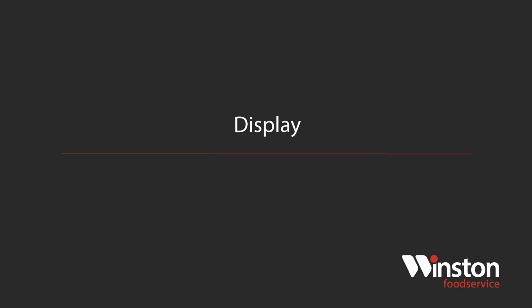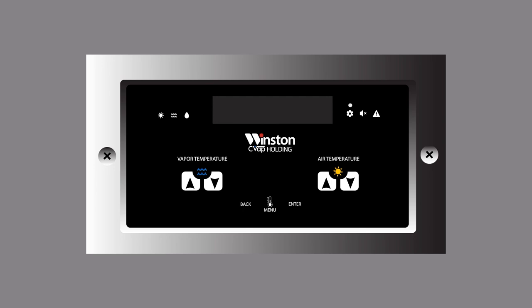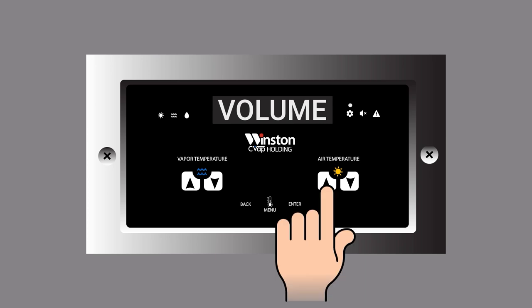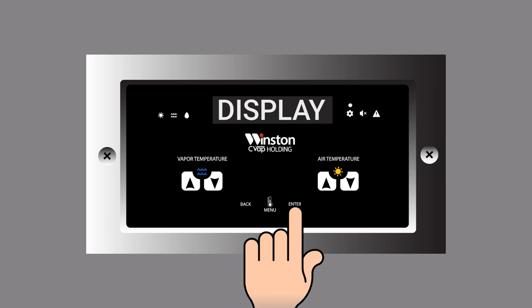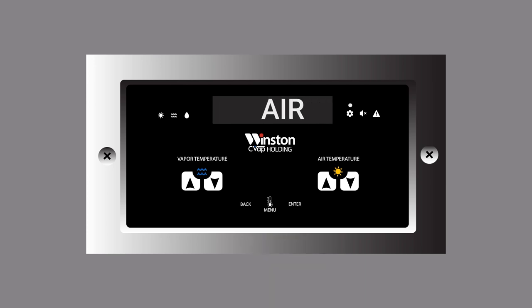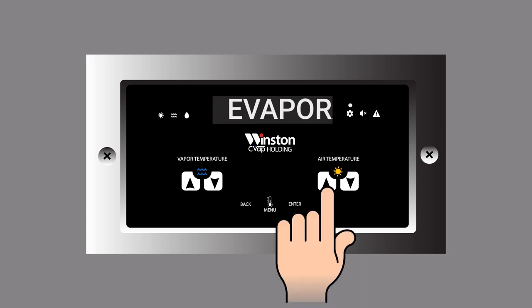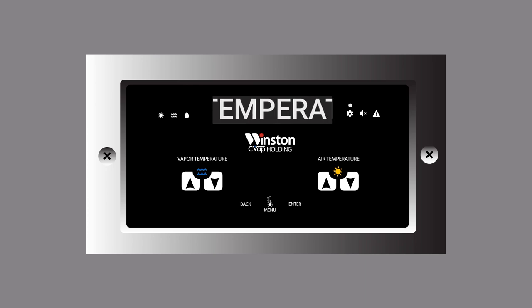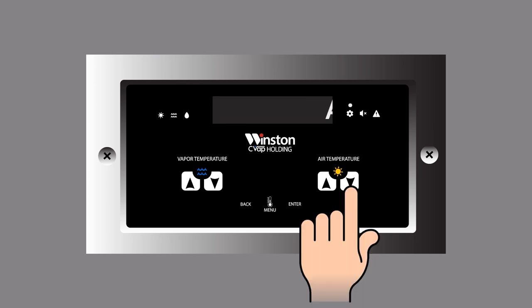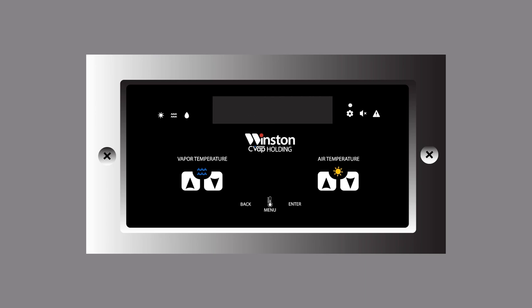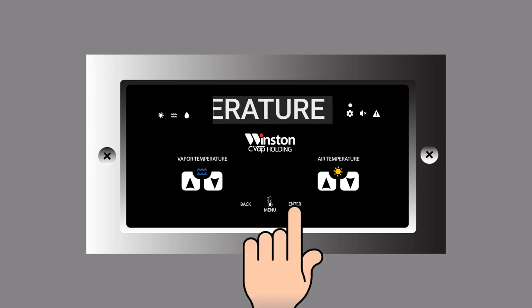Display. This allows the user to set the displayed temperature to either the vapor temperature, or the air temperature. With volume being displayed, press the air temperature up button and display will be displayed. Select Enter. Either air temperature or evaporator temperature will be displayed. Using the air temp up and down button, set the control to display either the air temperature or the evaporator temperature. Select Enter. Display will be displayed.